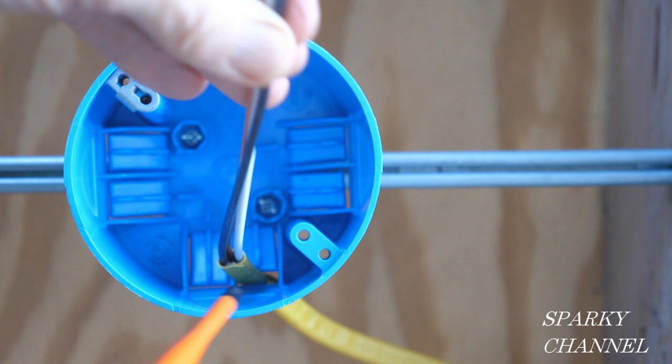And the main argument for the people who feel they shouldn't be is that the manufacturers of these boxes have already included these integral clamps in their box fill calculations. And the main argument that the people have who feel they should be included are that they're interior clamps. You know, they're not exterior clamps. You've got to call them interior.